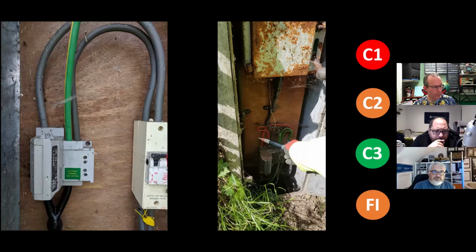Would you code that? So it's a PME. It looks like someone's maybe tried to see if there are connections on the right by drilling holes to see if there are terminals there. And then having figured out there aren't, they've taken it off and put it next to the neutral. Or they've just cut it off and realised it slots out: unplug the fuse and slide it out. You just slightly pull the fuse, there's no seal on it, and then you can pop it off, can't you?